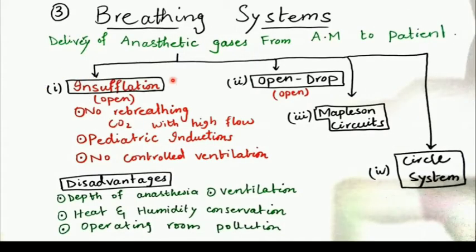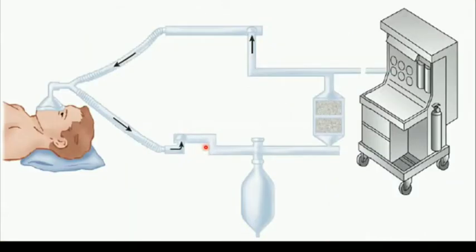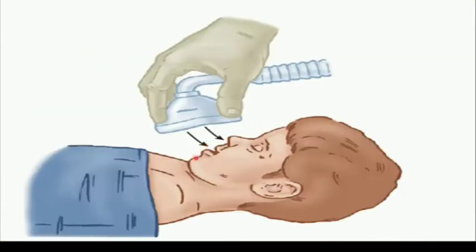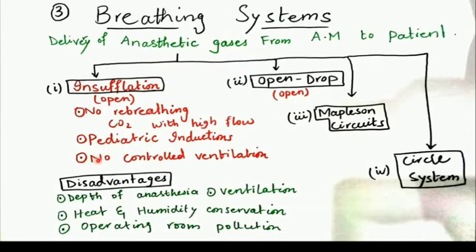The breathing systems we will discuss today are: insufflation, open drop, Mapleson circuits, and the circle system. In insufflation, there is no rebreathing of CO2 with a high flow of fresh gas. This type is normally used in pediatric inductions because children don't allow a face mask to be placed on their faces. Ventilation cannot be controlled by insufflation.